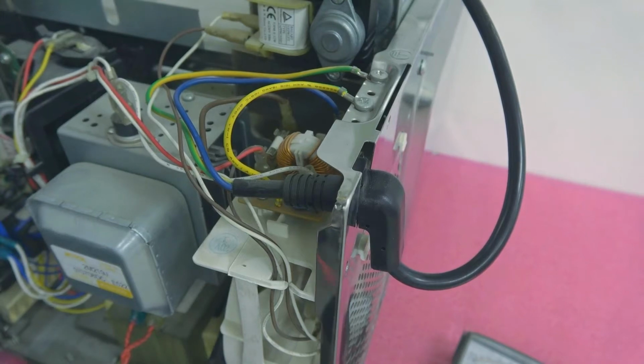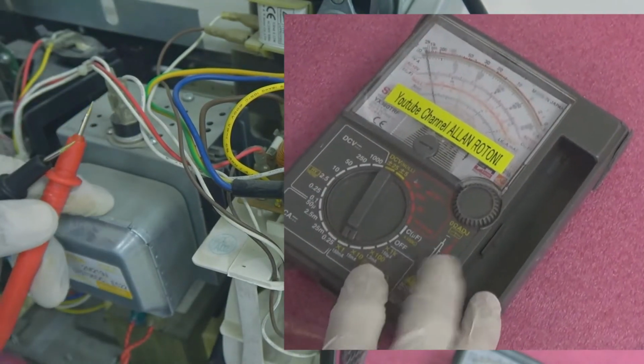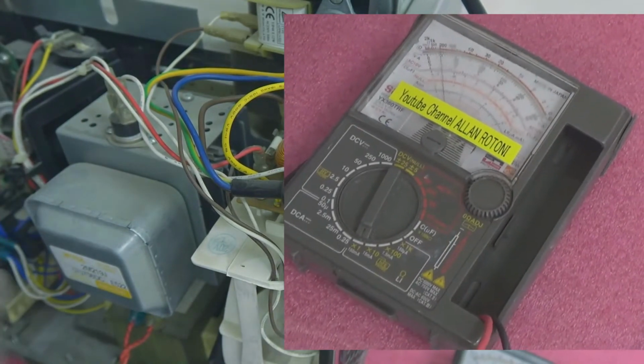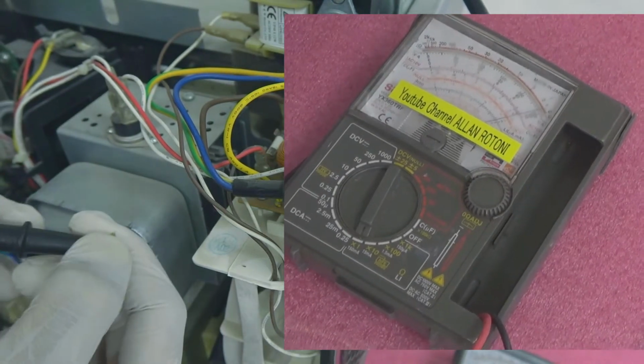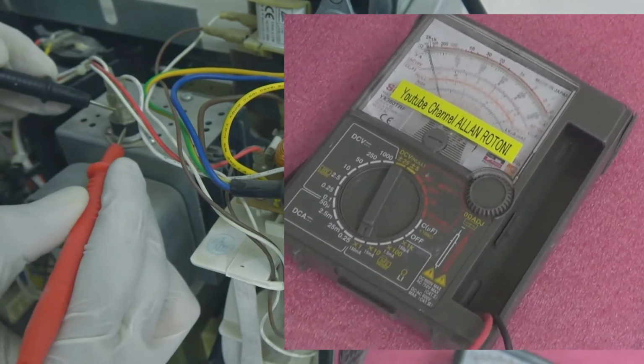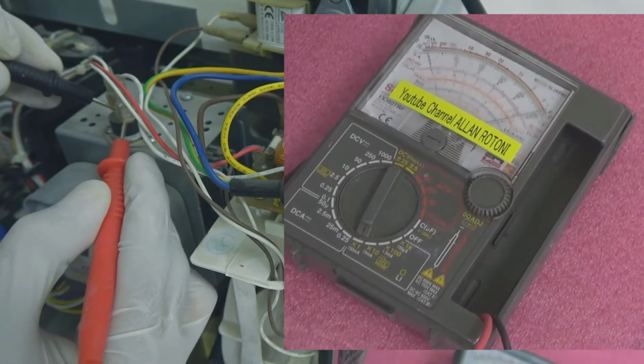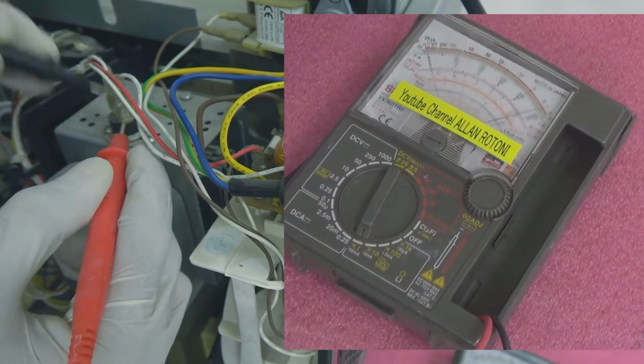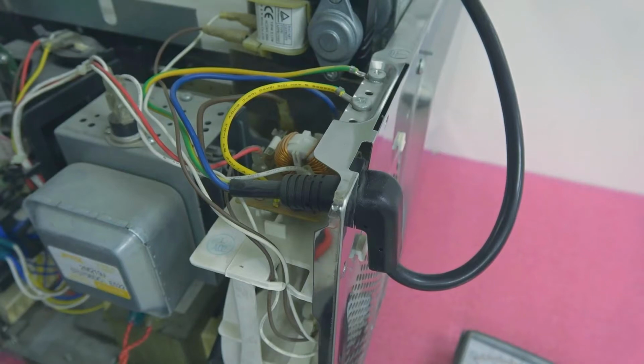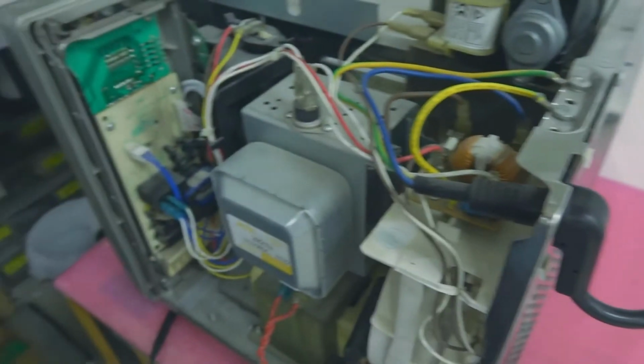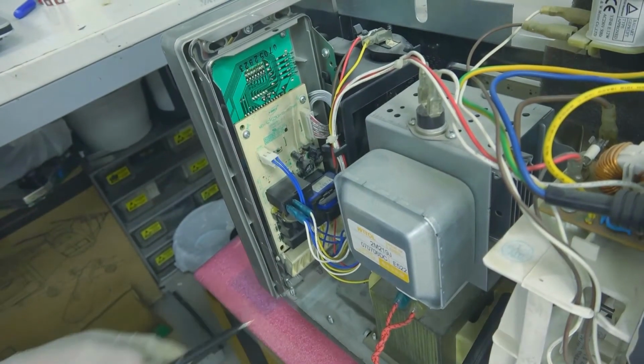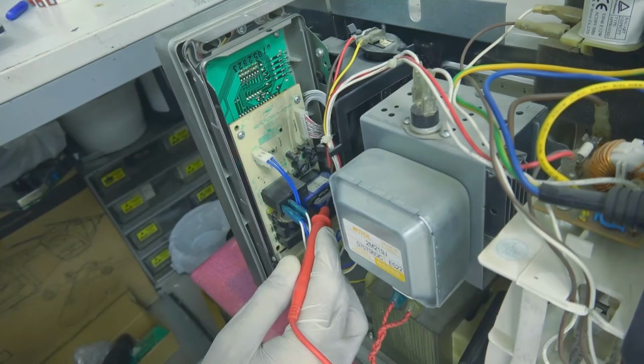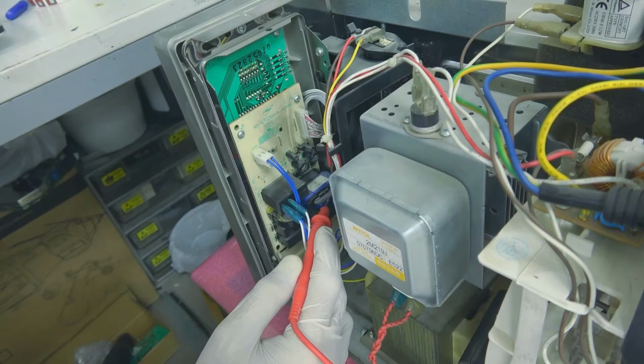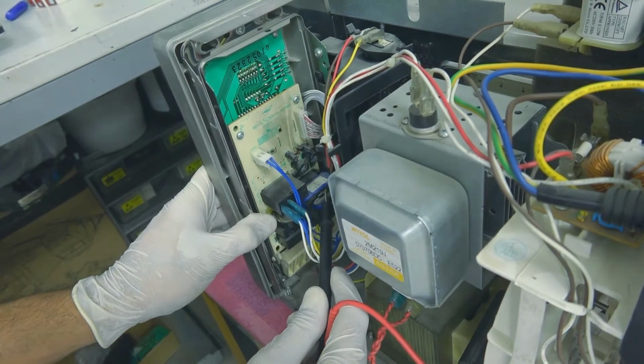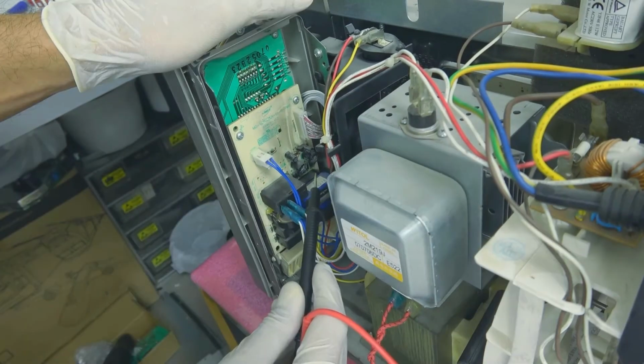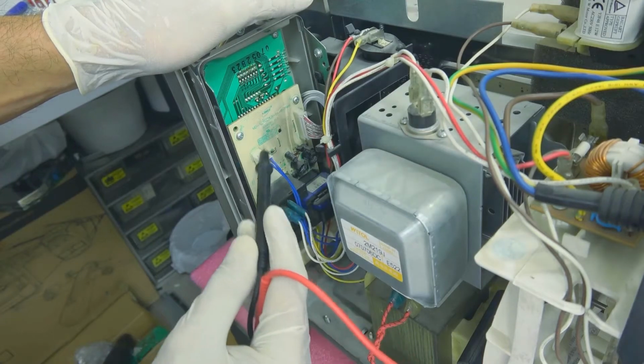The next thing you have to test is this thermostat or thermal switch. My tester setting is on ×1 just to test the continuity. And the thermostat is okay. So the next thing to be checked, if no power, is this standby power supply. It has a relay, and of course it has a transformer, the standby transformer. You must get continuity on this transformer, otherwise it will not power on.